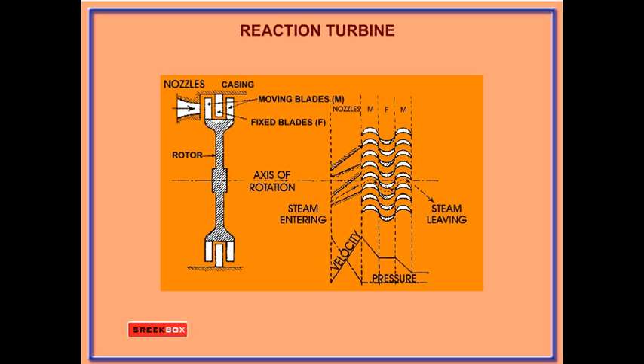The moving blade converts the kinetic energy into mechanical work with a decrease of velocity. But at the same time, steam expands as it flows over the moving blade and there is a fall of pressure. This produces a reaction on the blade by the expanding steam. Thus, in the reaction turbine, the steam expands both in fixed and moving blades continuously as the steam passes over them. Therefore, the pressure drop occurs gradually and continuously over both fixed and moving blades.